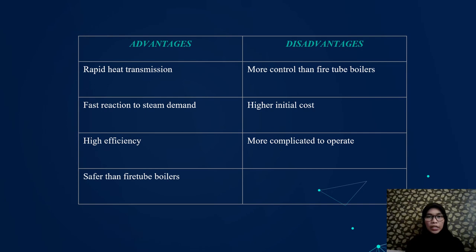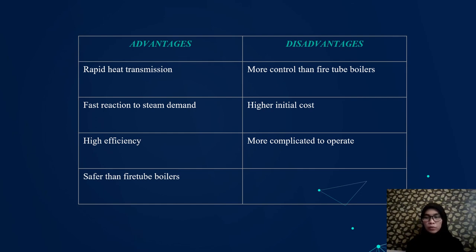For a water tube boiler, water flows through the tubes and is surrounded by hot combustion gas in the shell. Water tube boilers typically range in size from 500,000 to more than 20 million BTU input. Here is the water tube boiler diagram. The advantage of water tube boilers is high efficiency and fast reaction to steam demands. The disadvantage is that they are more complicated to operate and require more control than fire tube boilers.